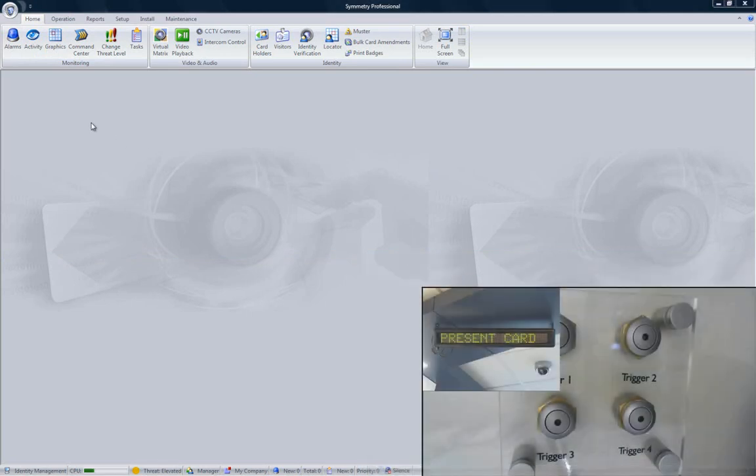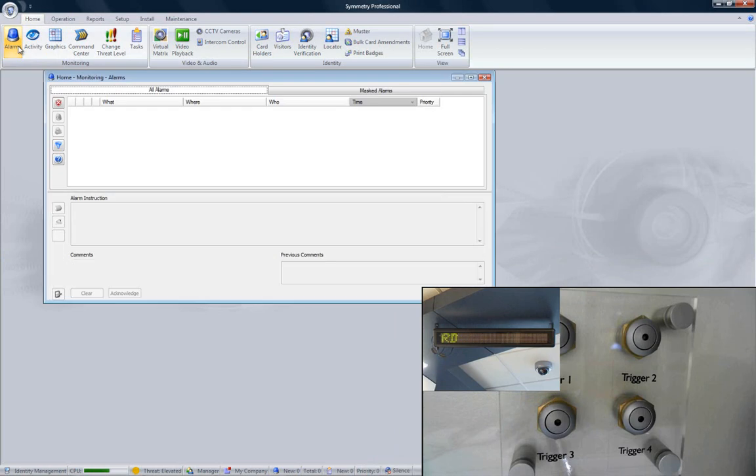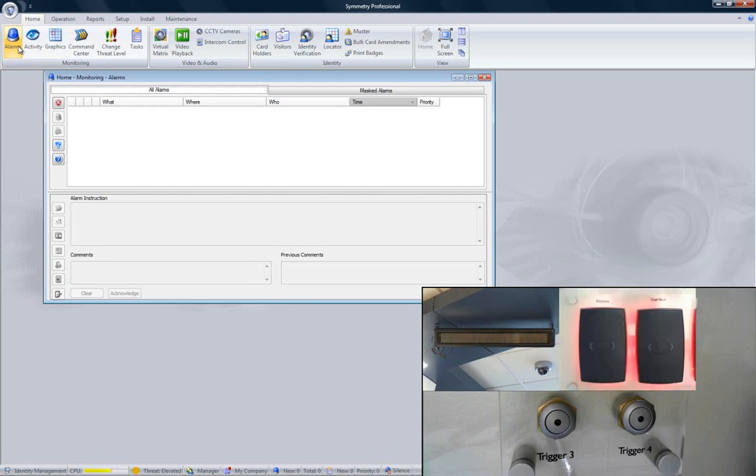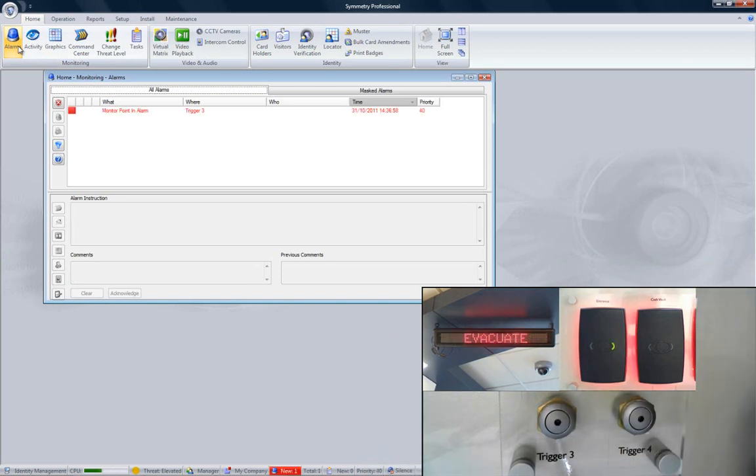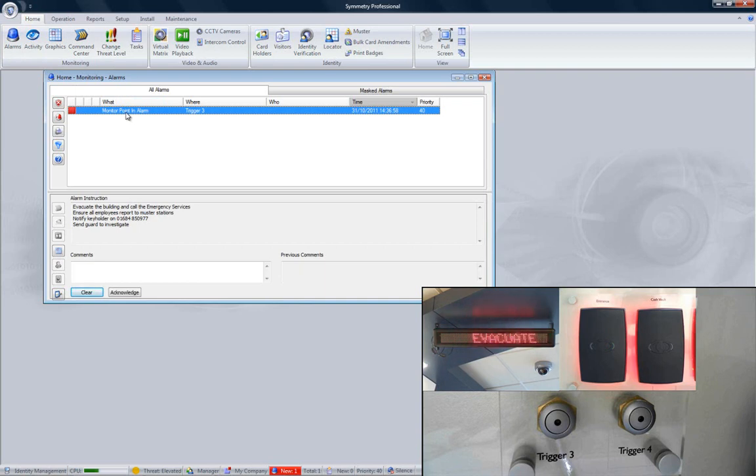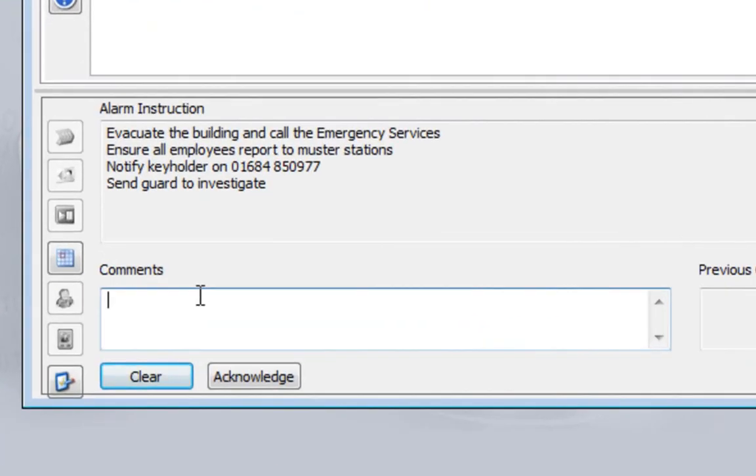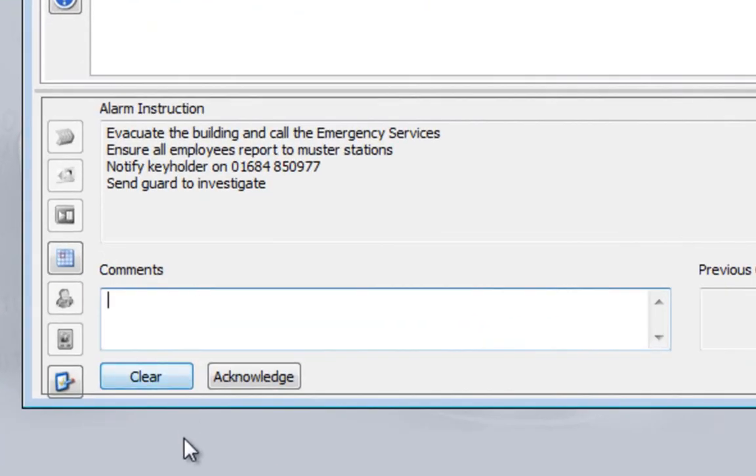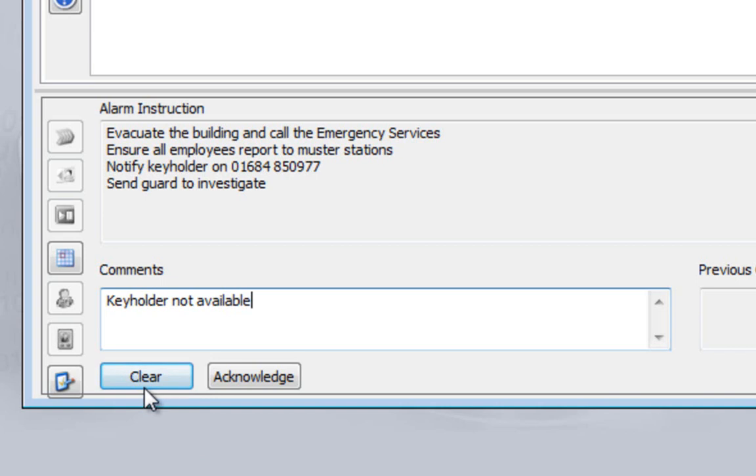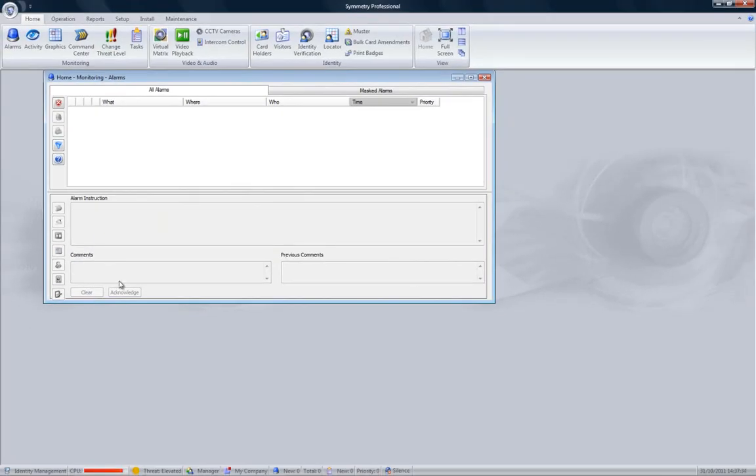If we run the same event again, but with the alarm screen showing, we'll see just one entry, the pressing of the switch. When we select the alarm, we see instructions to the operator informing him to call the emergency services, ensure that all employees are at their muster points, notify the keyholder, and send some guards out to investigate. Here we see the operator entering some text to explain what he did in response to the alarm, and then clear it.